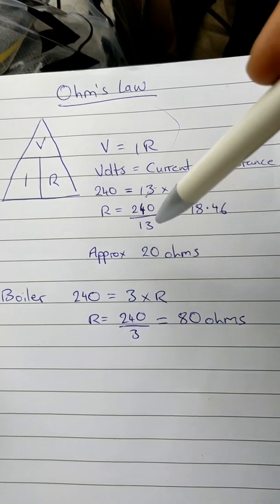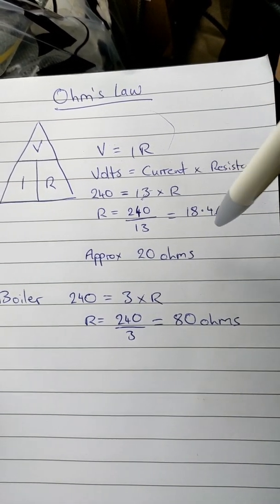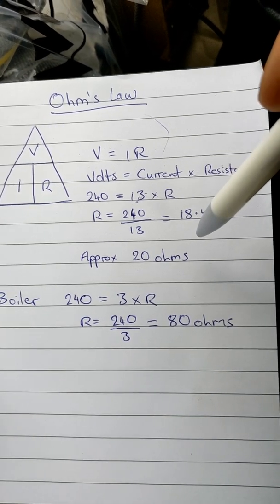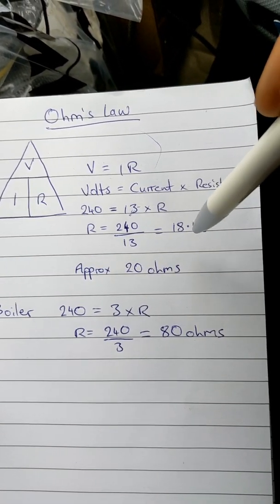Now, as long as you've got 20 ohms or thereabouts, this proves that the appliance that you're testing does not have a short circuit and it's safe to use. So it means when you switch it on, it's not going to go bang.